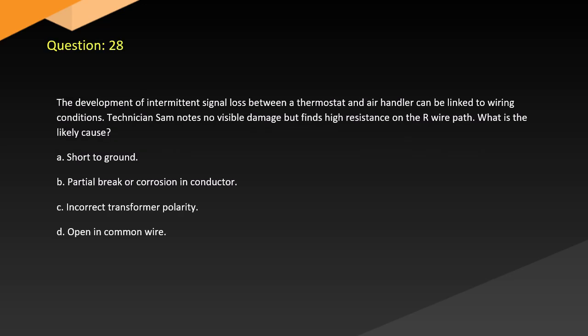Question 28. The development of intermittent signal loss between a thermostat and air handler can be linked to wiring conditions. Technician Sam notes no visible damage but finds high resistance on the R-wire path. What is the likely cause? A. Short to ground. B. Partial break or corrosion in conductor. C. Incorrect transformer polarity. D. Open common wire.